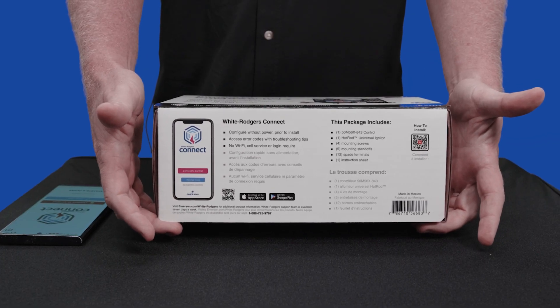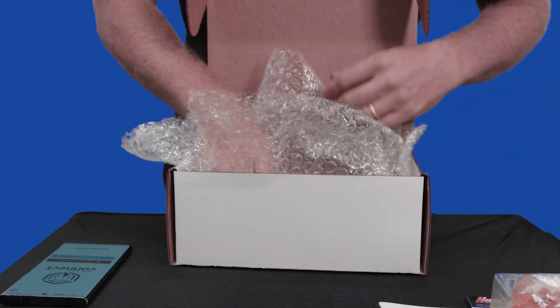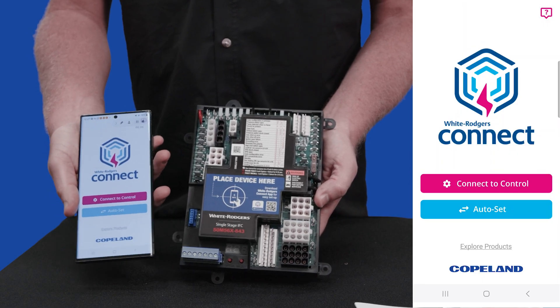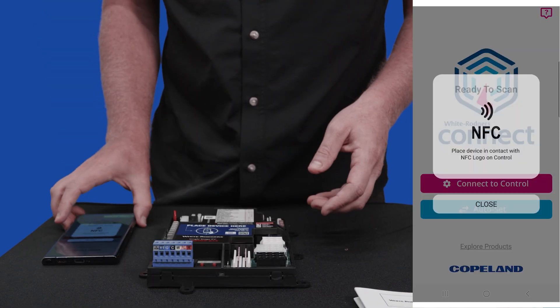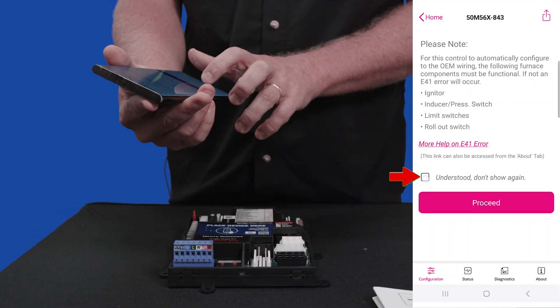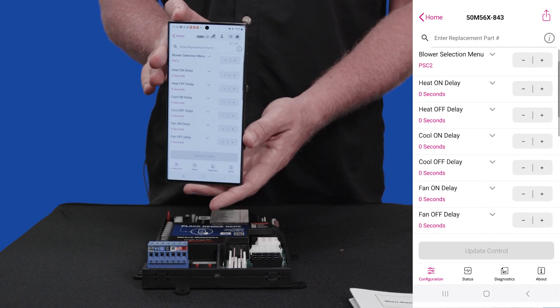Let's open this up and show you how easy it is to configure this board. I've already preloaded the White-Rodgers Connect app and used it a lot for service and other videos. All I'm going to do now is hit 'Connect to the control.' You see it pops up that near-field communication message showing you to put the center of the phone right on the device. Now you can see it's connected — it's pulled in the information about the control. It's telling you right here that you do need to confirm that everything is set up properly before you power on the equipment.